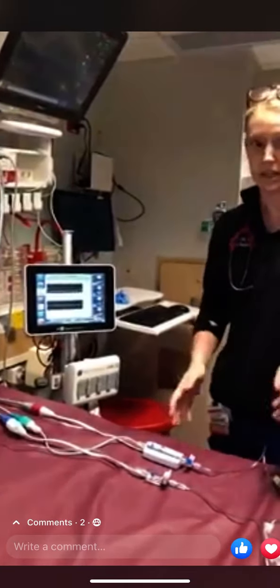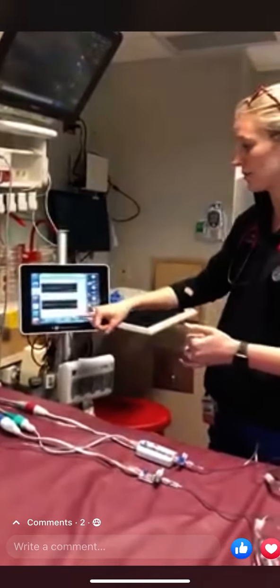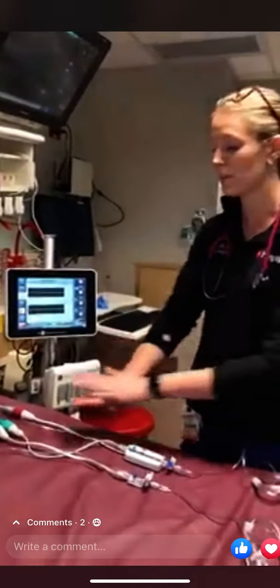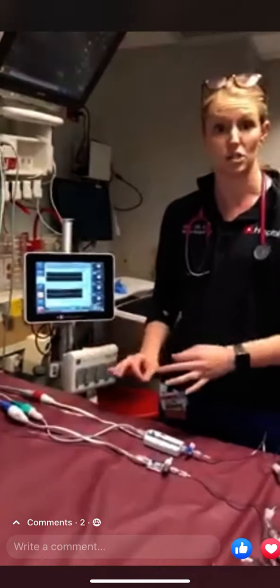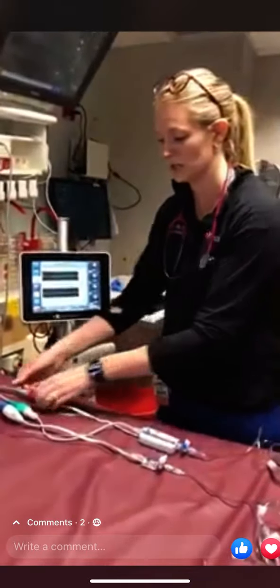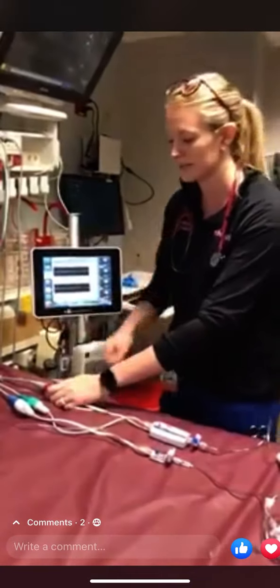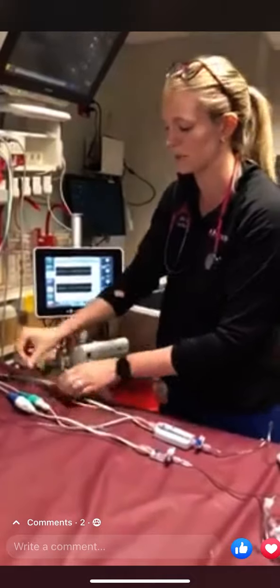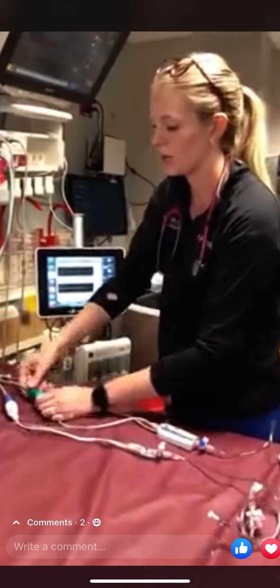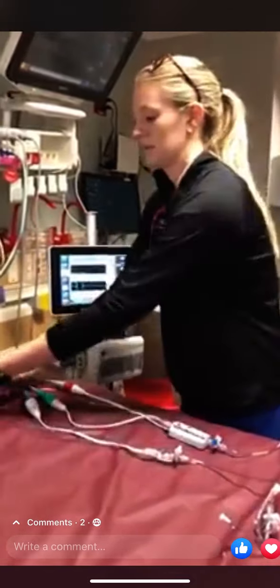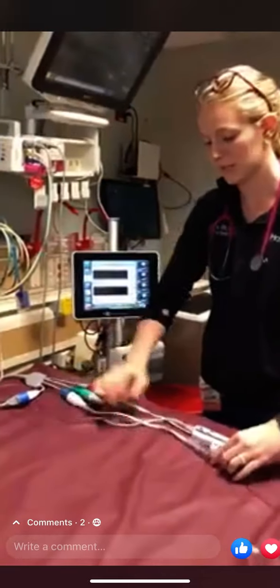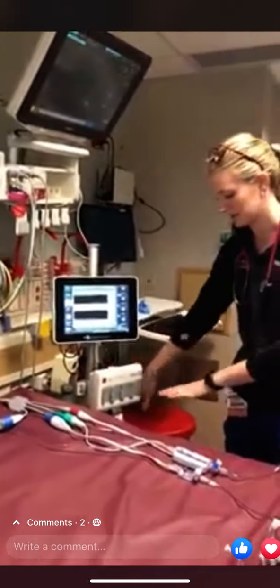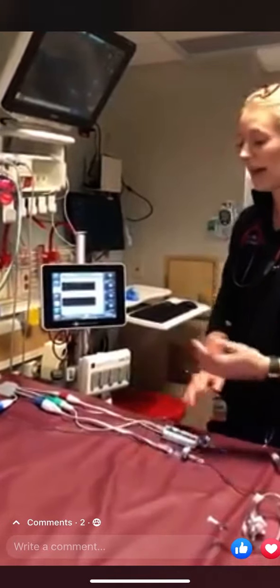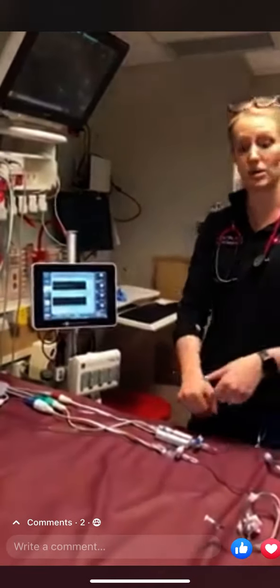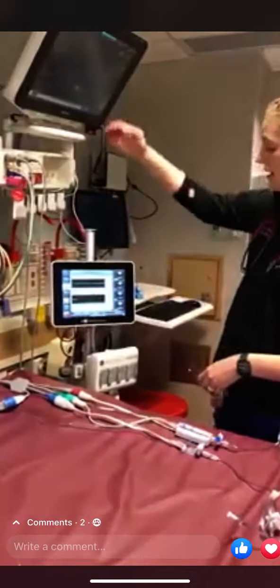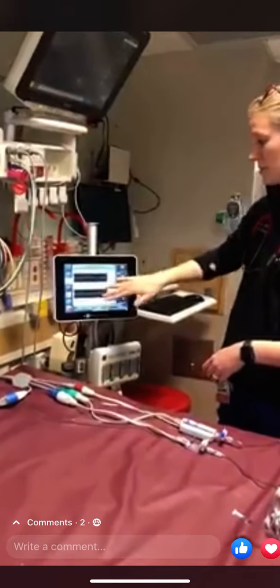Sometimes this can be tricky. If you don't have one of your 2 waveforms, all you have to do is unplug everything and replug it back in, and it should work. That's just the closest and easiest way to troubleshoot. So say hypothetically I didn't have my CVP waveform, I just keep everything exactly where it is, unplug it quickly, plug it all back in, make sure all my connections are tightened and that everything's connected at the bottom of the EV1000 as well. And then again, you just keep the patient flat, 0 both of them, which you would do here, and on the monitor, and then you should have waveforms on both fronts.